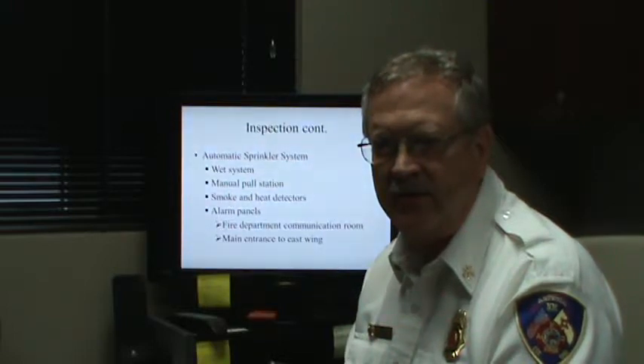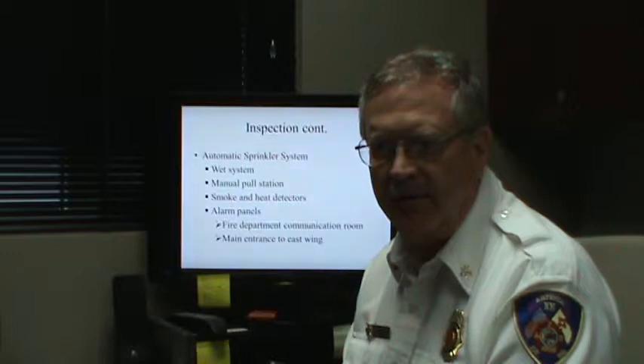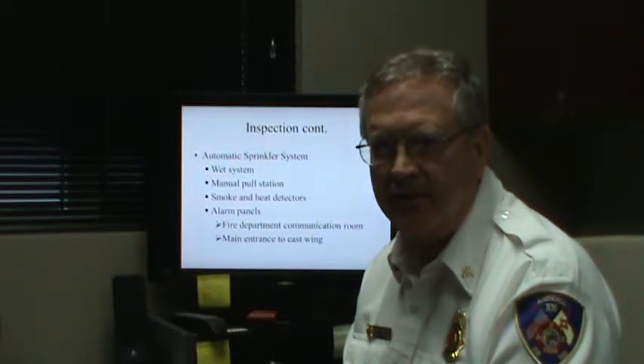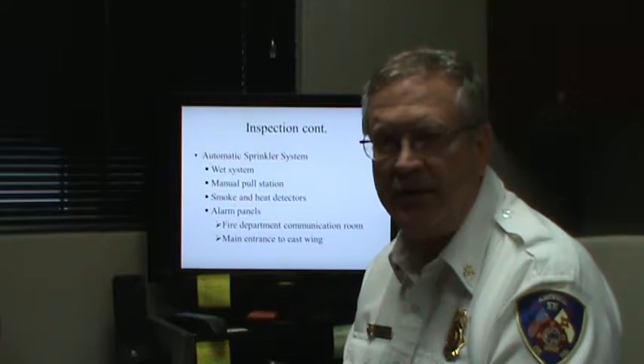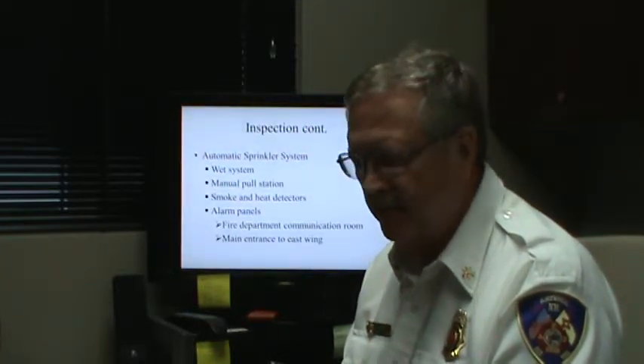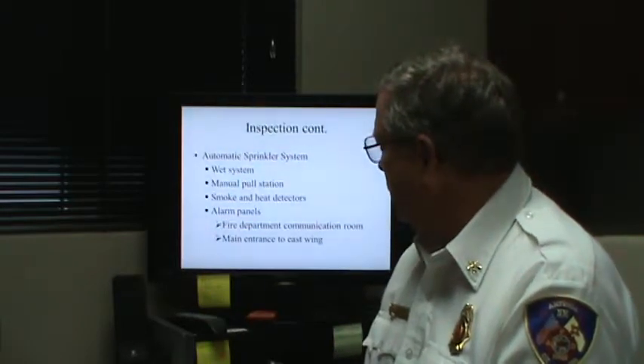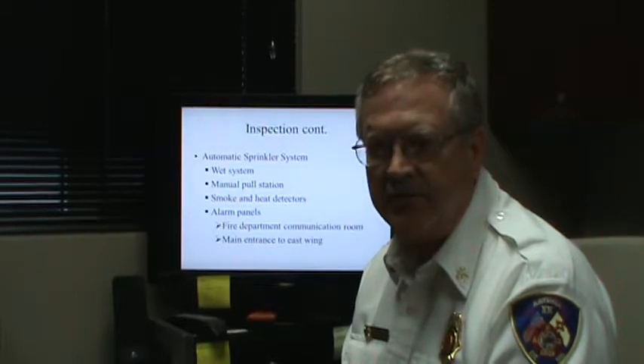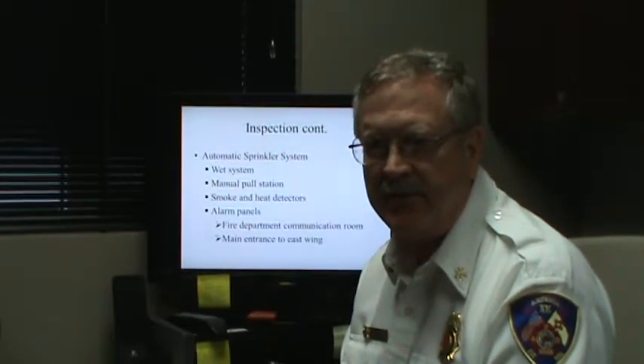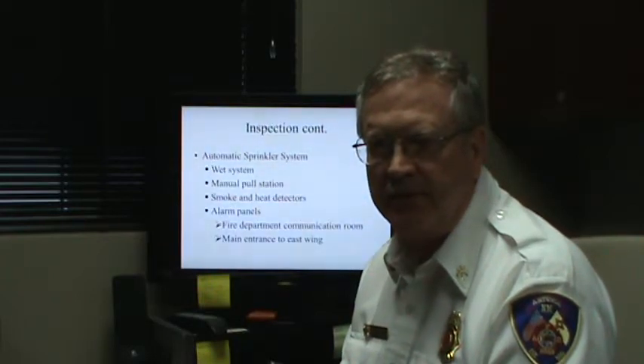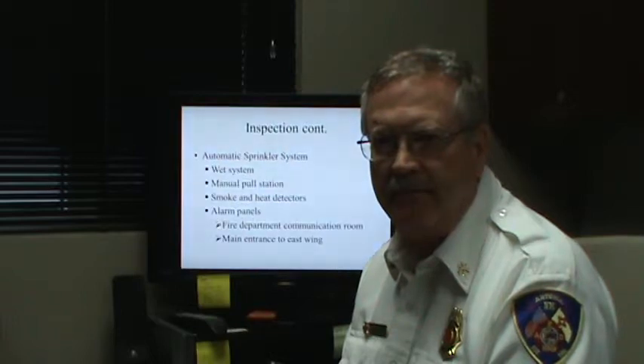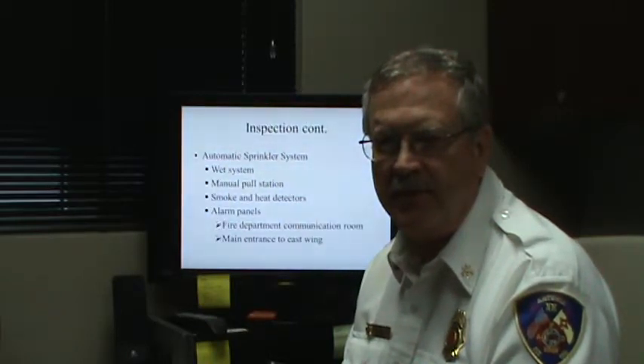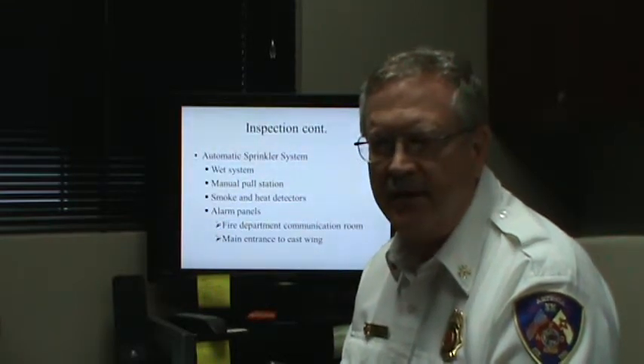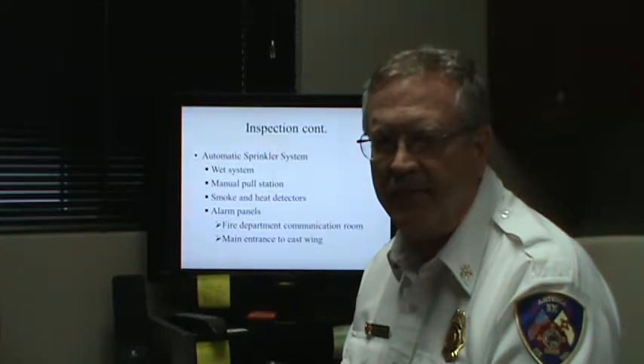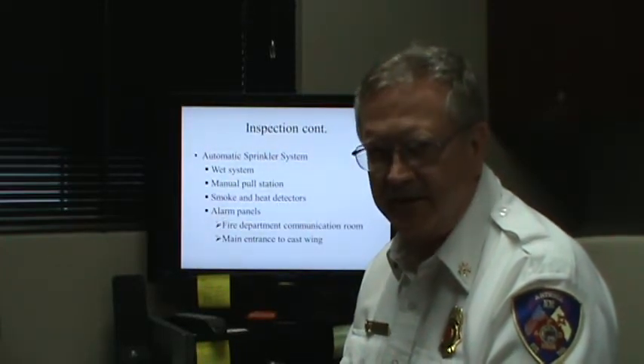I did check the panel, and it did show that I had an alarm, and it gave the number of the alarm, or the detector or the pull station. So it did give me the location of where I needed to go to reset the alarm if it was not a fire. Then I tested the smoke detector itself with industrial spray, and the detector functioned as it was supposed to. And the monitoring panel showed the number of the smoke detector, which would give me the location of where the trouble was. If it was a fire, then it would give me the location where the fire is, and I could direct the firefighters to the proper place.